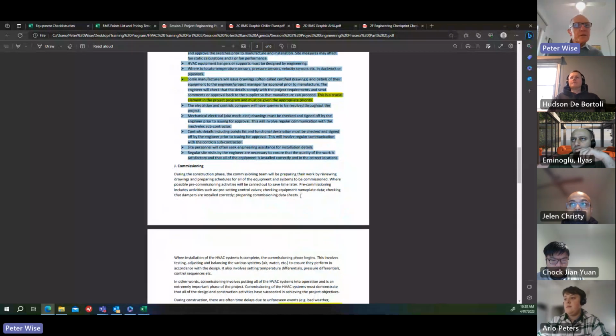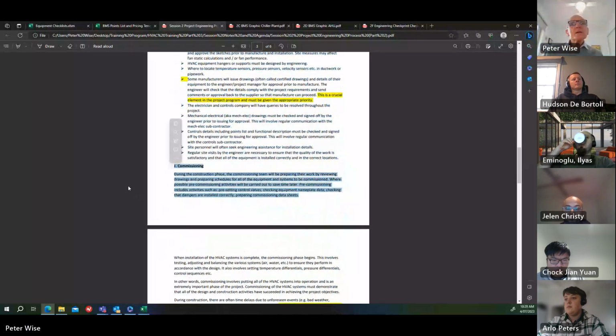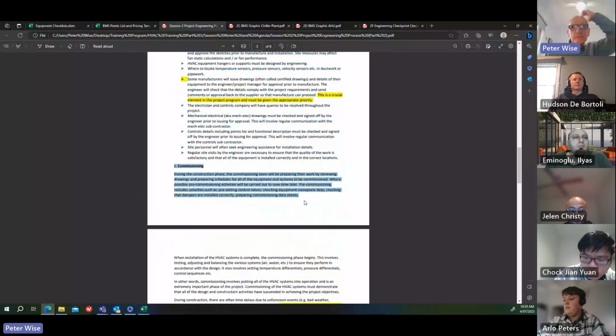Okay, so the construction's well underway or getting close to completion. Commissioning starts. During the construction phase, the commissioning team will be preparing their work by reviewing drawings and preparing schedules for all of the equipment and systems to be commissioned. So when possible, pre-commissioning activities will be carried out to save time later, so they can get on site and start doing things before construction is completed. Pre-commissioning includes activities like pre-setting control valves, or balancing valves, that should be, sorry.